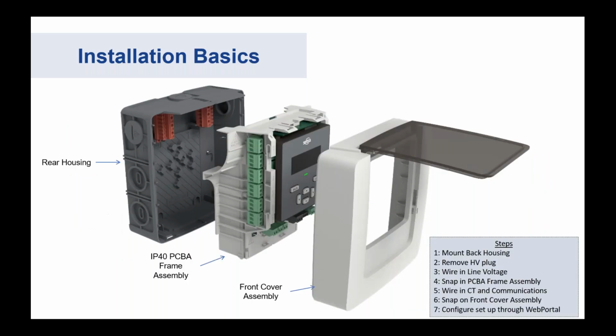Some of the installation basics. So how this meter would get installed is there's a rear housing, and you can see the two red terminal blocks for your voltage inputs. You would install this to the wall, and then you'd bring your high voltage to those red terminal blocks, either 1 or 2.